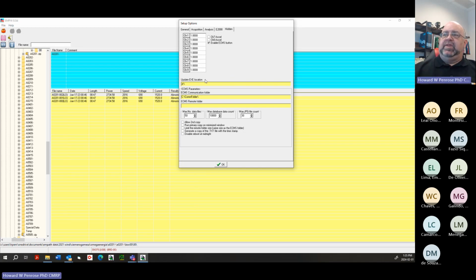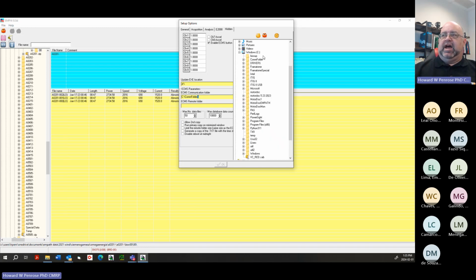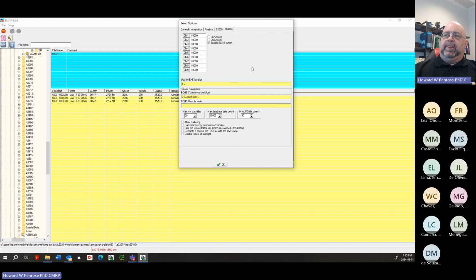When you do that, you want to create a folder called a communication folder. You don't have to call it the COM folder, but if I double click, I can go down and select whatever folder I want to call it. That's where all my data is going to reside, up to so many sets of data. I can also do a second folder or a backup folder. This will keep up to 1,000 sets of data for each one. We use that for when we have continuous monitoring set up.